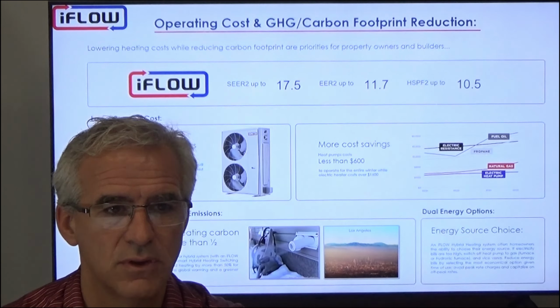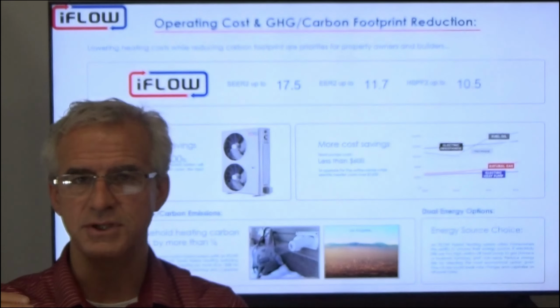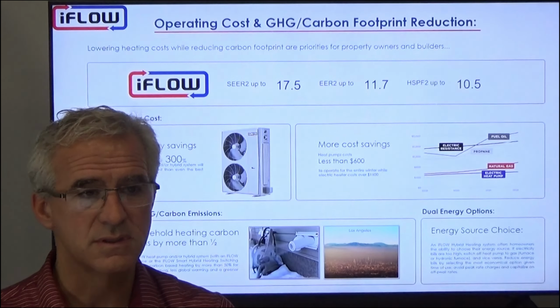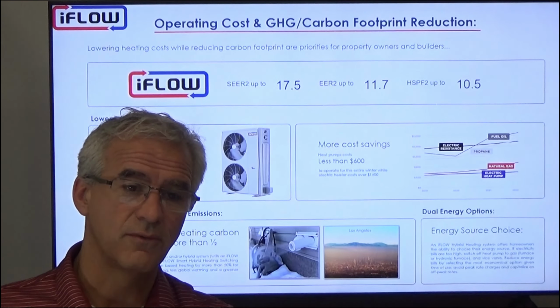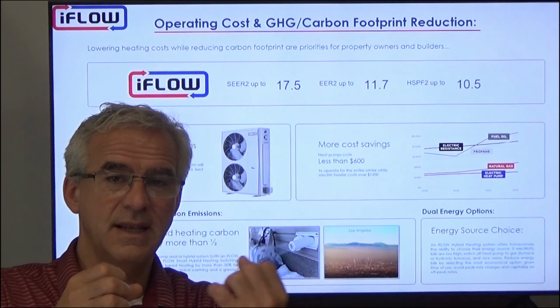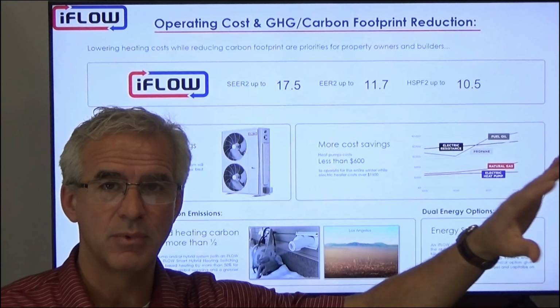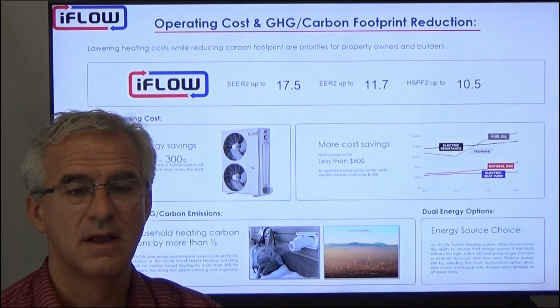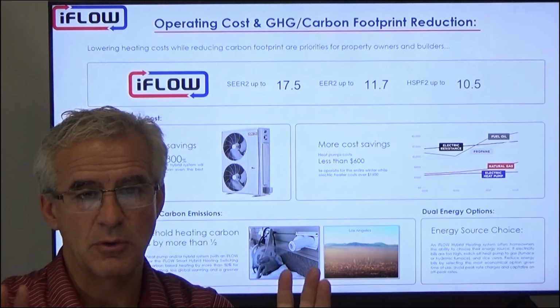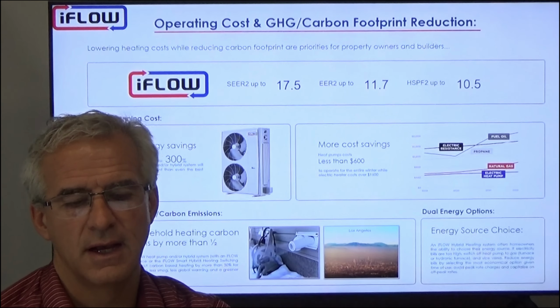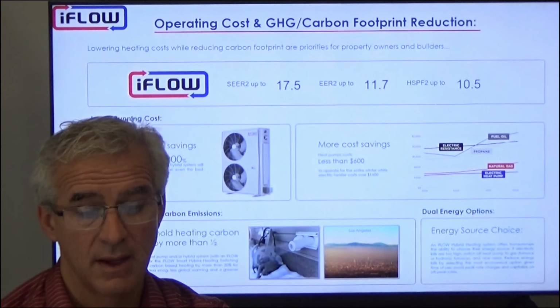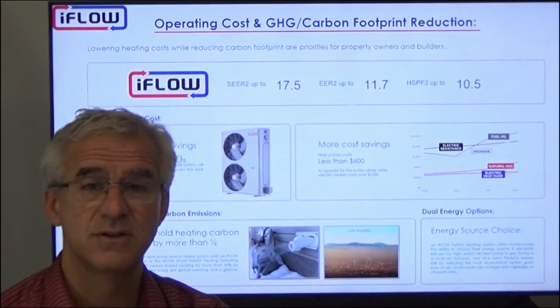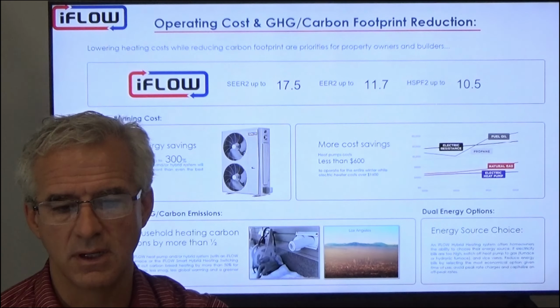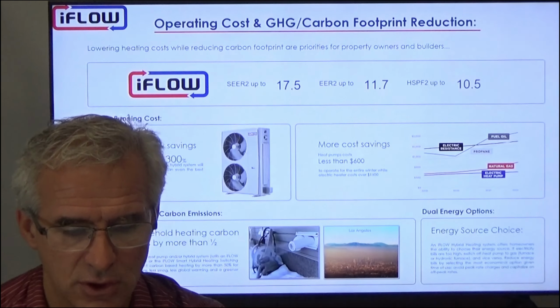If we look at a gas-based system, even though it's not measured in COP, if we look at the concept, energy in versus energy out, a typical gas furnace, let's say it's a condensing furnace at 95% AFUE, 97, 98% AFUE, it's still under 1. So what it means is for each 100% of energy in, we're getting 90%, 95% or 97% into the heating, but we lose that little bit, that 2, 3, 4, 5% to the exhaust, and that's on the gas system. So comparing metrics, if we were trying to give an equivalent COP to a gas-based system, it would typically be under 1, but close to 1 for condensing units. So when we look at a COP of 3 or a COP of 2, that's 200% more, 300% more than what we would typically get on the gas-based system. So definitely some energy savings potential there.